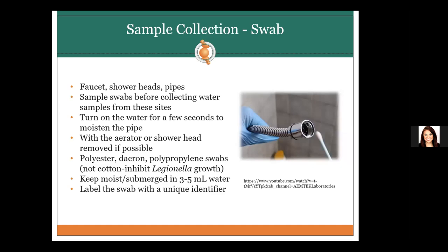For sample collection using a swab, these are more ideal for faucets, shower heads, and pipelines. Sample swabs before collecting water in case there's bacteria in a biofilm on the surface. Turn on the water a little just to get it moist, and if there's a shower head, try to remove it to get inside the piping. Polyester, Dacron, or polypropylene swabs are best — try not to use cotton-based swabs because they can inhibit Legionella growth. Keep the sample moist with a little water from the source you're testing, and label each swab with the sampling location.